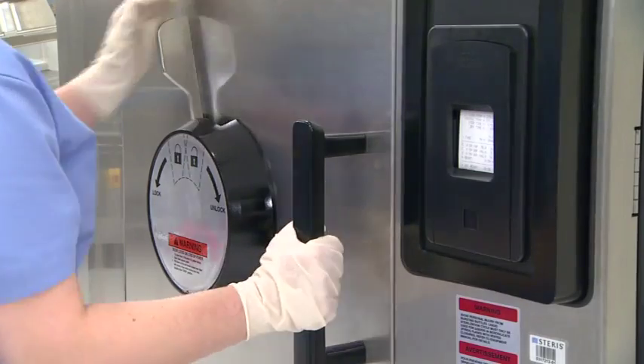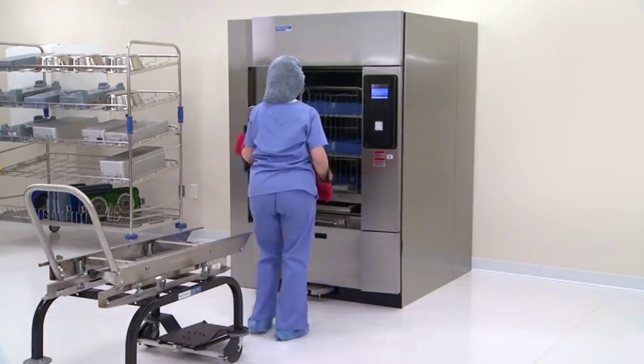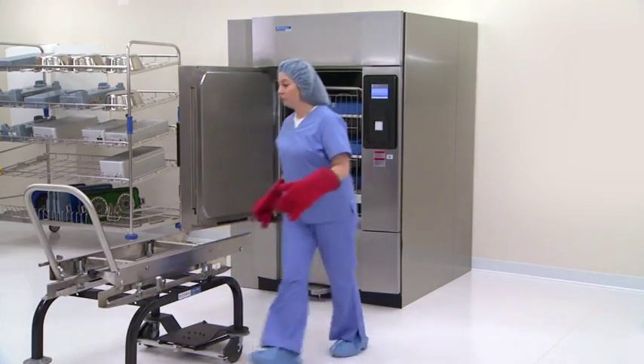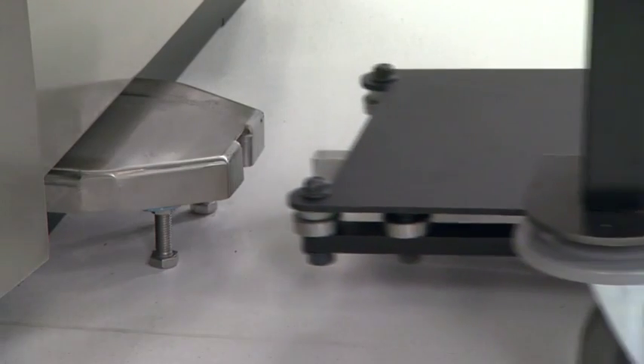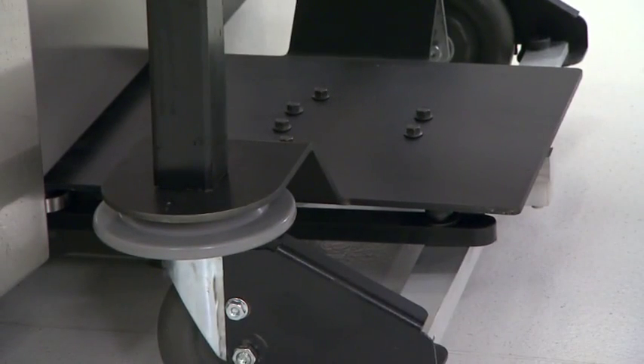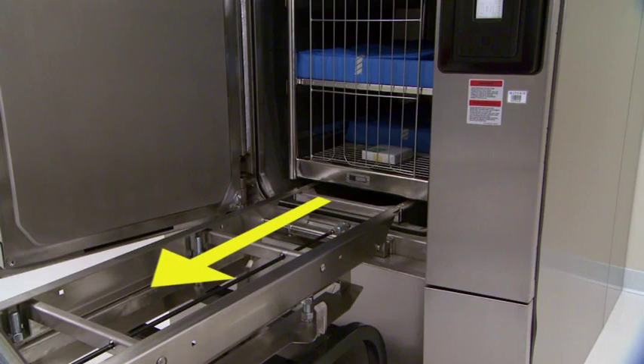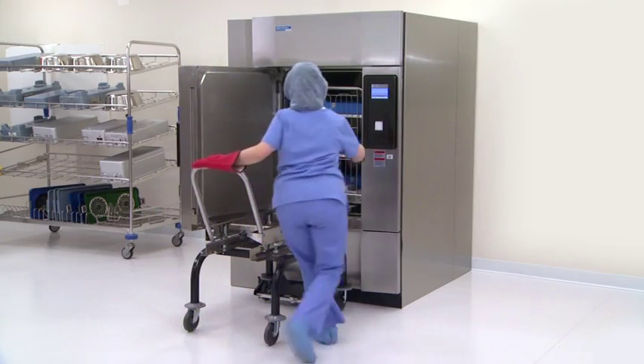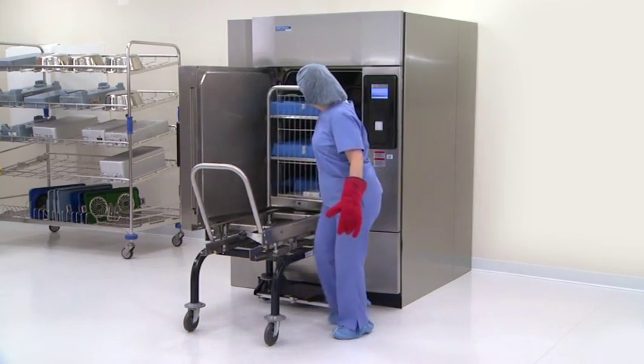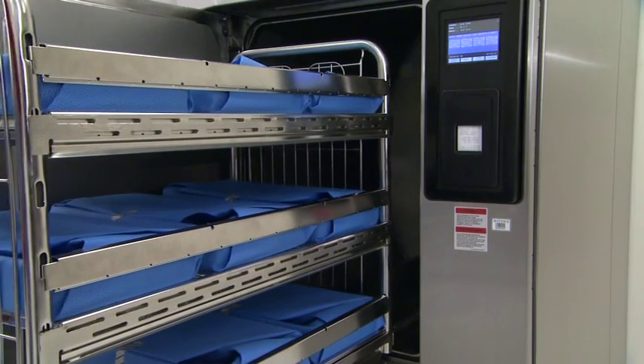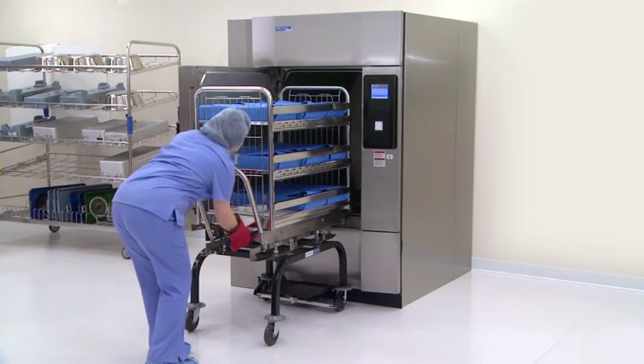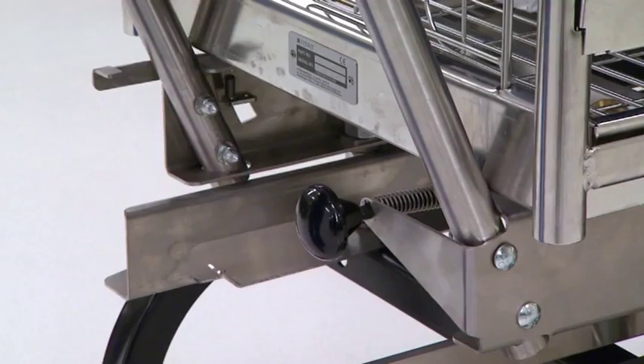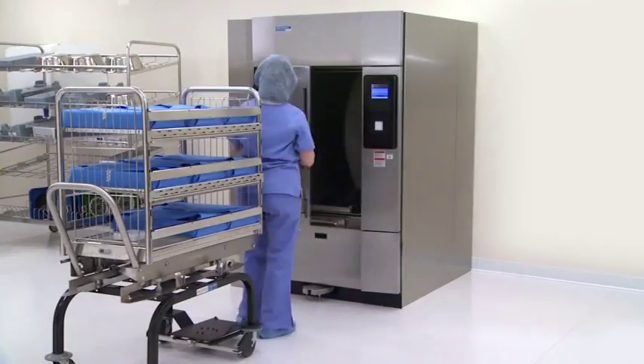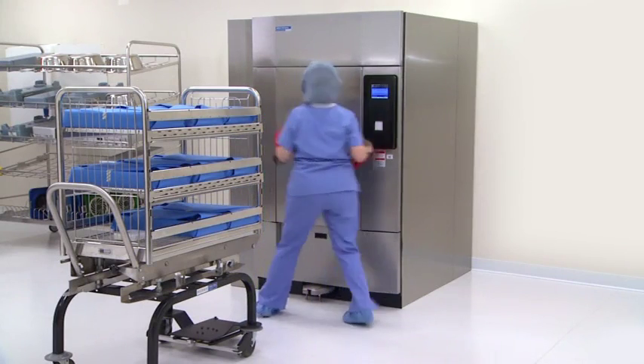To unload the carriage, first open the chamber door. Move the transfer carriage forward until it aligns with the dock assembly at the floor. The latches on the transfer carriage will engage with the bracket on the chamber end ring. Verify the transfer carriage is latched to the chamber end ring by pulling the transfer carriage backward. The transfer carriage should remain stationary. Once the transfer carriage is securely latched, grasp the loading car handle and carefully pull the loading car from the chamber onto the transfer carriage until the transfer carriage latch engages to the loading car. Disengage the transfer carriage latches from the track inside the chamber by pulling the carriage latch knob. Close the chamber door and transfer the load from the sterilizer area.